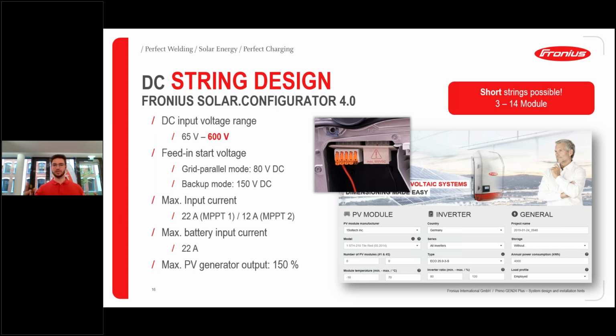The Primo is a little bit of a smaller product, and therefore we have it only up to 600 volts. So very important to remember this when designing a system with this product. 65 to 600 volts. And actually, when we think about this, we have a very broad input voltage range. So this is really a huge range. And actually starting from 65 volts on to have the tracker tracking, we can actually do very short strings as well. So this we can see in the red box on the top right here.